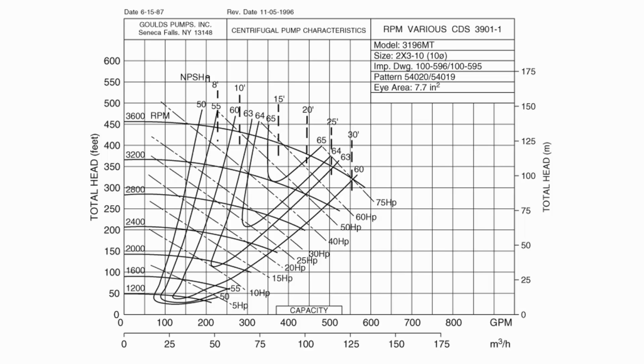Another thing for you to notice is these curves that look kind of like contour lines. Those are the efficiencies. They give you a general idea of the efficiency from the input power to the output power that the pump is actually putting into the water. For instance, if we were operating this pump at 3,200 RPM and 300 gallons per minute, so if we follow that 300 gallons per minute up to the 3,200 RPM, then that would be 64% efficient. And so then you'd have an idea of how much power you need to provide to the pump.